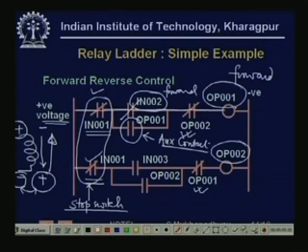So the moment this gets supply or becomes 1, this is going to be excited. So this will be closed. Now even if you remove this switch, it is a push button. So you have to press it and then you can release it. You can't keep holding it. So you press it once and immediately, even if you leave it, the motor will keep running. That's the arrangement that we have to make.